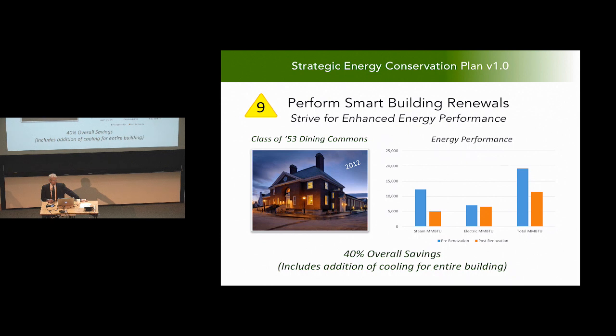I'm showing an example of the Dining Commons project, which was renovated over 2 summers several years ago. It was a complete and full renovation of the building architecturally and mechanically, and it now incorporates key energy features, including variable flow kitchen exhaust hoods. We installed a heat recovery system, which is pretty uncommon in that type of application, recapturing the waste heat of the refrigeration systems in the building and using that to preheat domestic hot water and a number of other things.